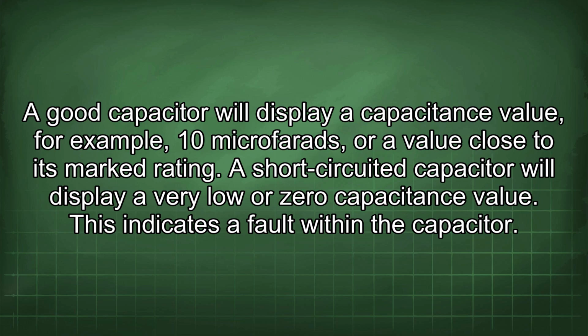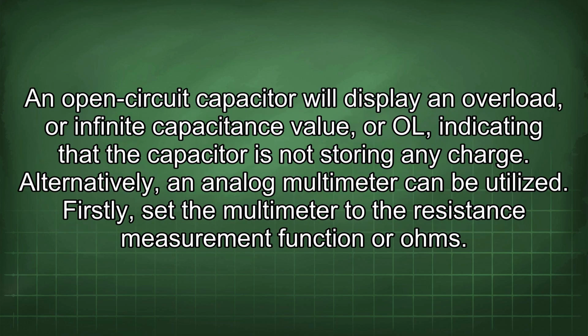A short-circuited capacitor will display a very low or zero capacitance value. This indicates a fault within the capacitor. An open-circuit capacitor will display an overload or infinite capacitance value, indicating that the capacitor is not storing any charge. Alternatively, an analog multimeter can be utilized.